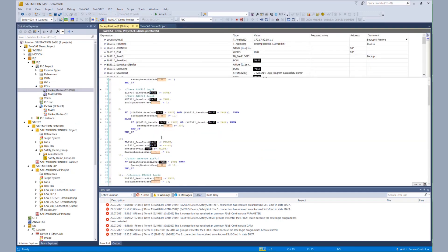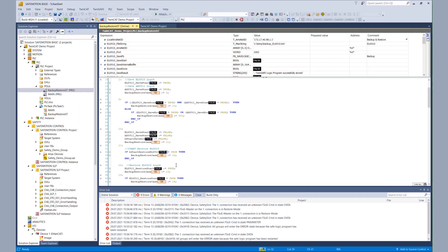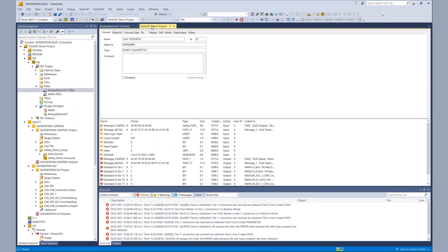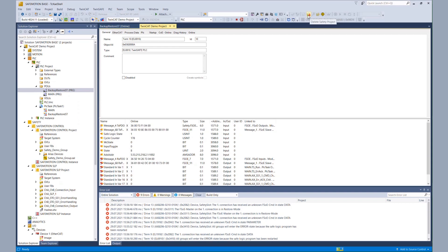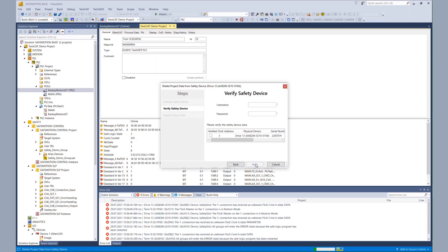Now we can go to our PLC part, and via our implemented trigger, we can start the restore for the EL6910. The corresponding function block is called, and now the restore is finished. We go back to the process image of the EL6910 and see that the EL6910 is talking again to the EL1918 and the AX8000.